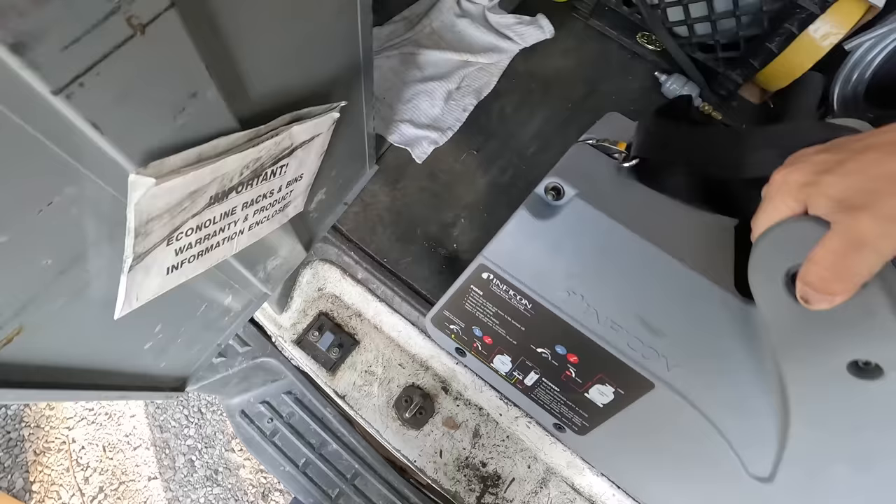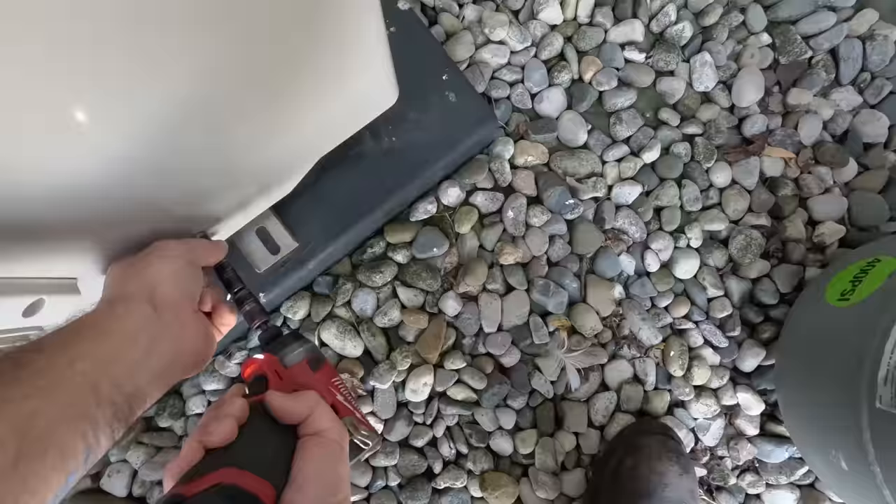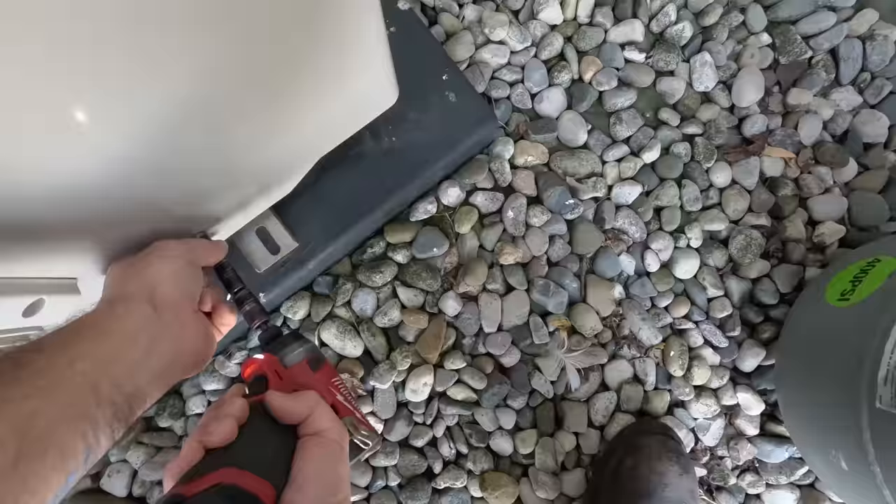I've been pretty happy with these Inficon recovery machines. They've been pretty good — I'll leave links down below. It's a little bigger size-wise than the Appion, but I think it does it a little quicker. This is going to be your liquid line right here because it's feeding your electronic expansion valves. Here's your suction — that's your true dedicated suction line right there.